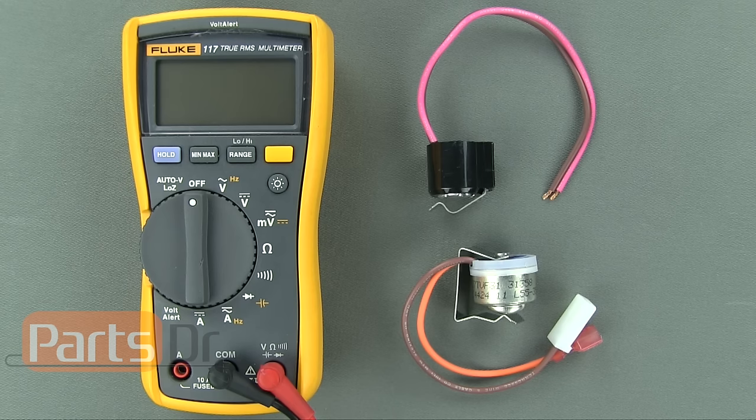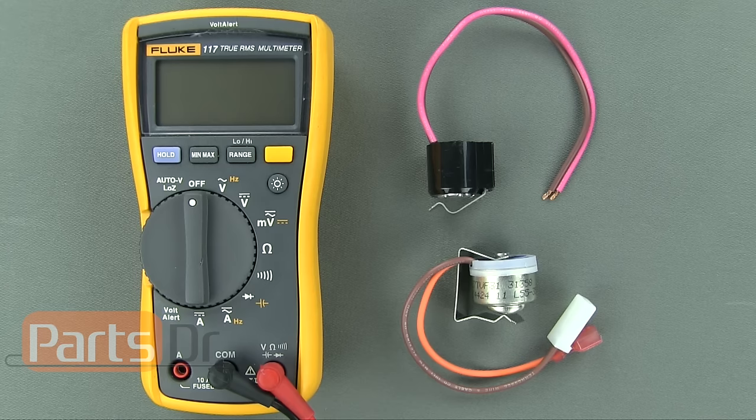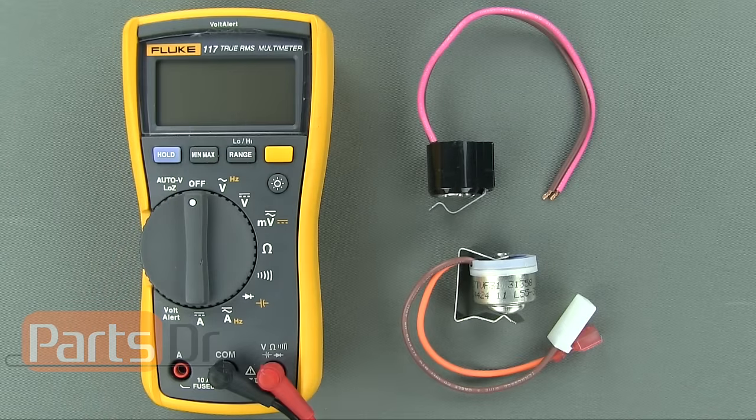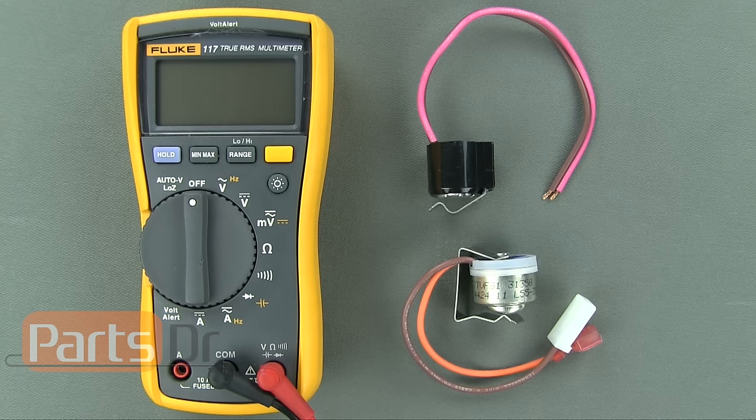If you take a look at the side of the defrost thermostat, you should see some letters and numbers that look like this: L 55 minus 35 F. The first number next to the L is the limit temperature that the thermostat opens up at. In this case, it is 55 degrees Fahrenheit.